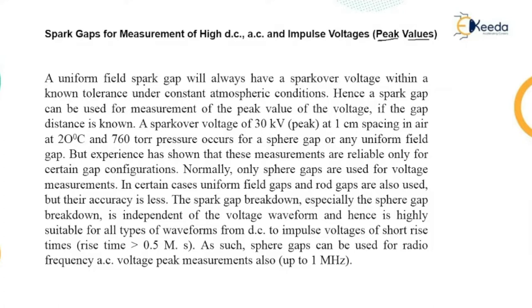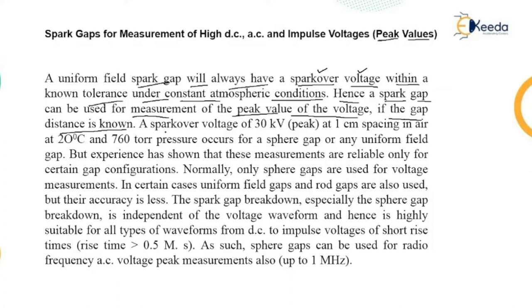A uniform field spark gap will always have a spark over voltage within a known tolerance under constant atmospheric conditions. These atmospheric conditions are very important and will be noted in the consecutive slides. Hence a spark gap can be used for the measurement of peak value of the voltage if the gap distance is known.